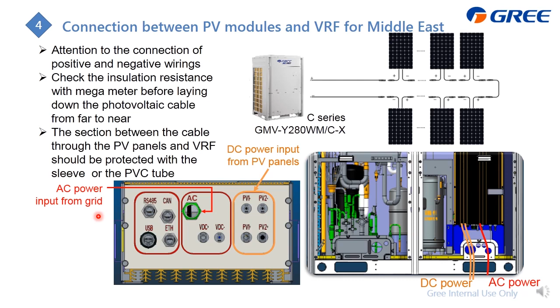Next is the detail of how to do the wirings, and this example is for this model. After you do the wirings of the PV panels, just pay attention, don't mix the positive and negative. Also check the isolation resistance with the mega meter before laying the cable down. And this cable will also require protection.